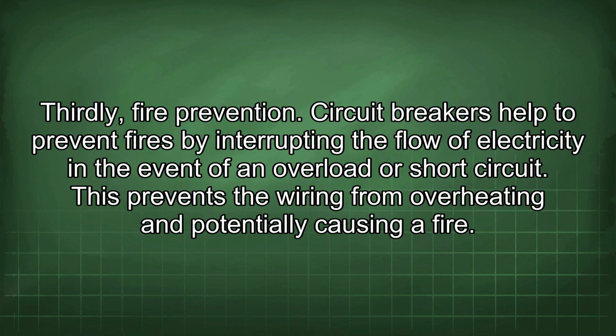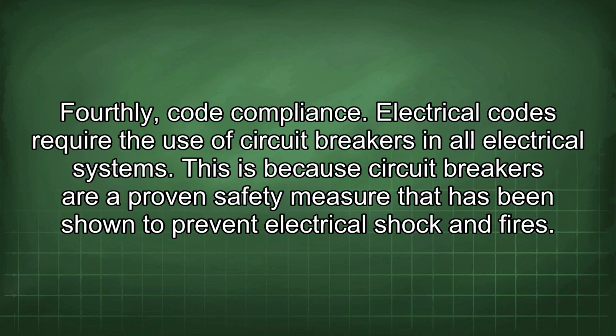Thirdly, fire prevention. Circuit breakers help to prevent fires by interrupting the flow of electricity in the event of an overload or short circuit. This prevents the wiring from overheating and potentially causing a fire. Fourthly, code compliance. Electrical codes require the use of circuit breakers in all electrical systems. This is because circuit breakers are a proven safety measure that has been shown to prevent electrical shock and fires.